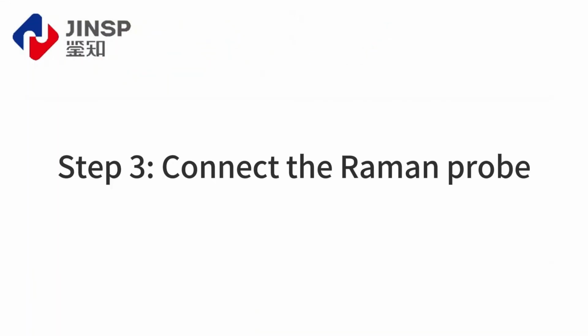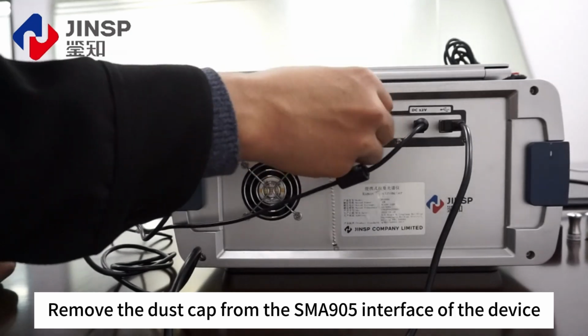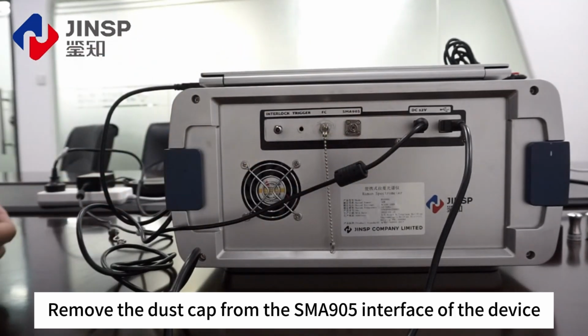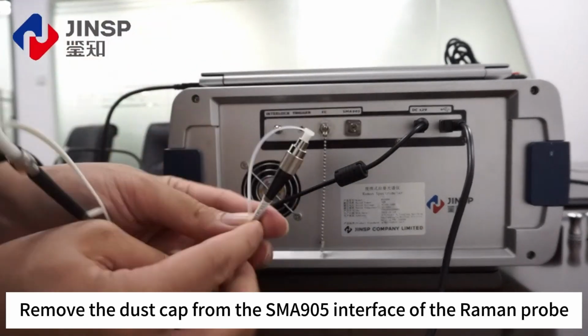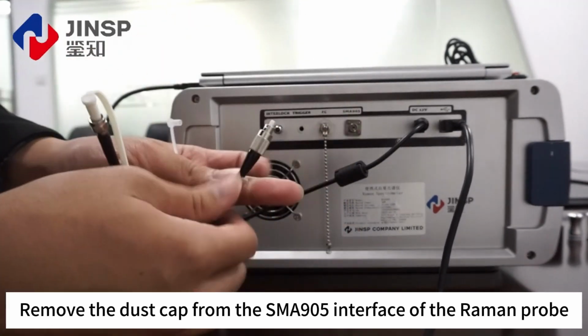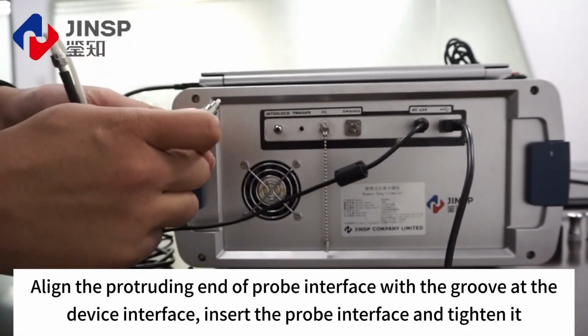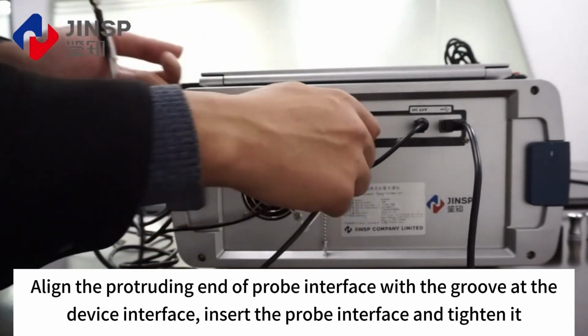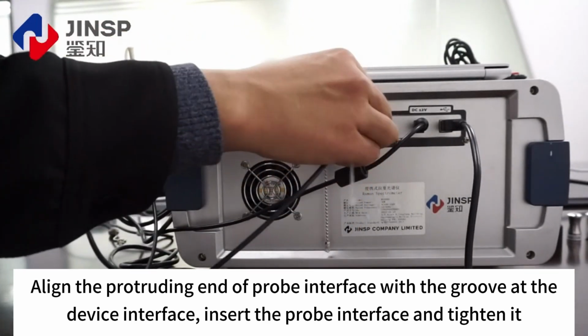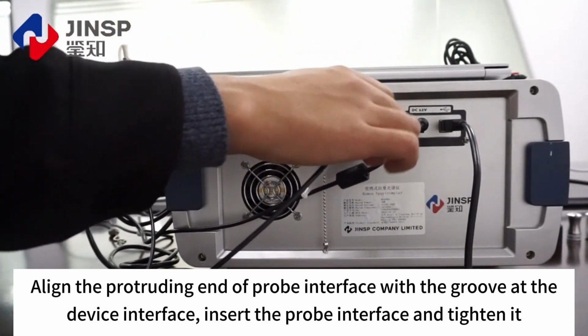Step 3. Connect the Raman probe. Remove the dust cap from the SMA905 interface of the device. Remove the dust cap from the SMA905 interface of the Raman probe. Align the protruding end of probe interface with the groove at the device interface. Insert the probe interface and tighten it.